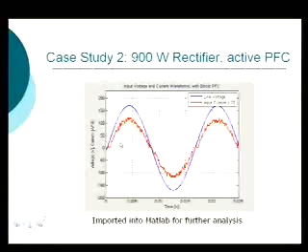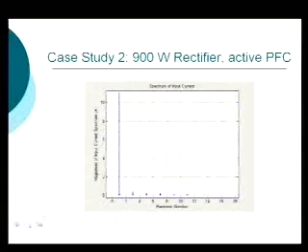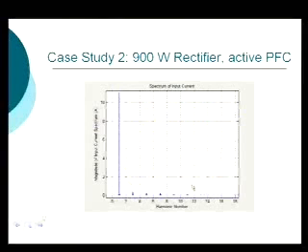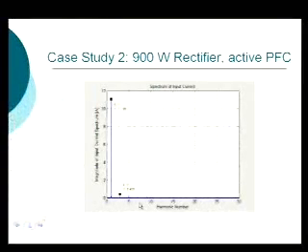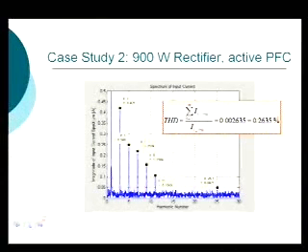Taking this into MATLAB, you can see the same thing. Note the symmetry and that they're basically in phase. Looking at the spectrum again, the fundamental is approximately the same as before, but now the harmonics are greatly reduced. Measuring them for a THD calculation, we see a THD of 0.26%, so this is pretty much a sine wave.